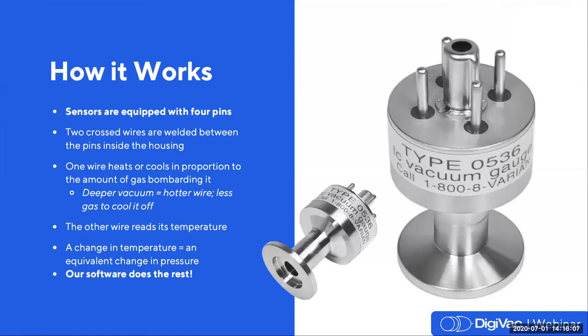Here we have pictured an Agilent 536 vacuum sensor, which is often paired with our gauges. The 4 pins on top of the sensor are electrically connected inside by 2 thin filaments welded together inside the sensor body. We use the circuitry of the gauge to heat one of those filaments. Then that wire will heat or cool in proportion to the amount of gas bombarding it.